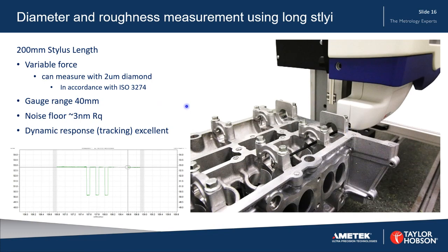But the thing here is that because this stylus is longer, it will of course be heavier. But the PGI NOVUS that's being used here to do these measurements is able to control the stylus force and to keep that stylus force to the correct stylus force in accordance with the ISO recommendation, excuse me, for roughness measurement.